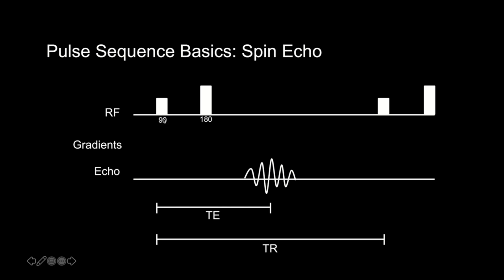Over time after this 90-degree RF pulse, there's going to be longitudinal relaxation back towards the z-axis and transverse relaxation, or T2 relaxation. Also remember that there is transverse decay due to magnetic field inhomogeneities — what we introduced as T2 star. Nuclei experiencing a lower magnetic field precess slower, get out of phase, and lose signal in the transverse plane. After all of that relaxation, we then apply a 180-degree pulse — also called a rephasing or refocusing pulse — which occurs halfway between the 90-degree pulse and the echo, at one half of TE.